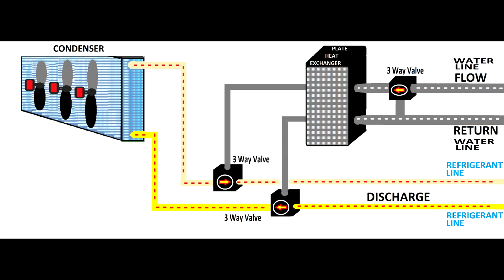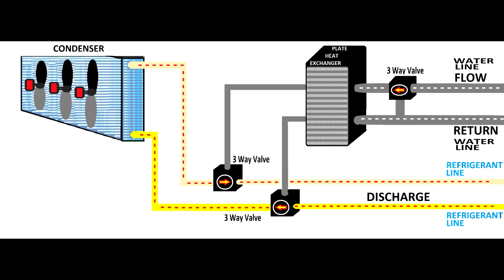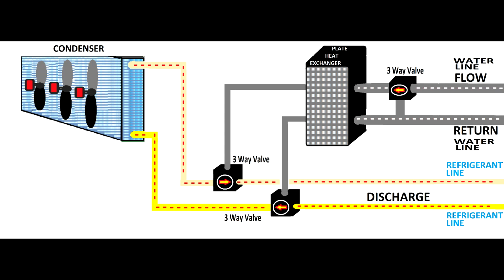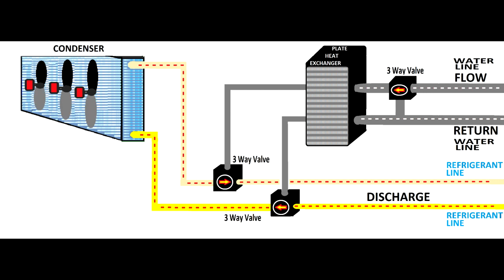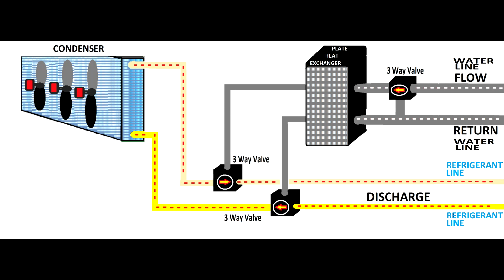If there is no heat demand in the store, then we'll divert the refrigerant through the condenser, and the condenser will take over. The condenser will control the refrigerant pressure, so we won't have any refrigerant passing through the plate heat exchanger.